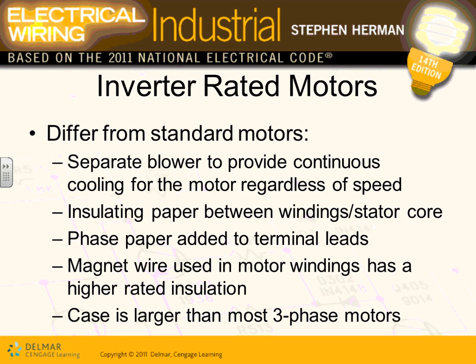So the only thing I want you guys to remember, very important, being designers, is when you specify a motor, most likely you don't, but you're going to see it on the mechanical engineering spec: inverter-rated motors, so it can be driven peacefully by an inverter, a VFD. And by the way, they are fat and fluffy. They're large. The inverter motors, for the same size, are bigger. Anybody know why? They put more insulation between the windings.